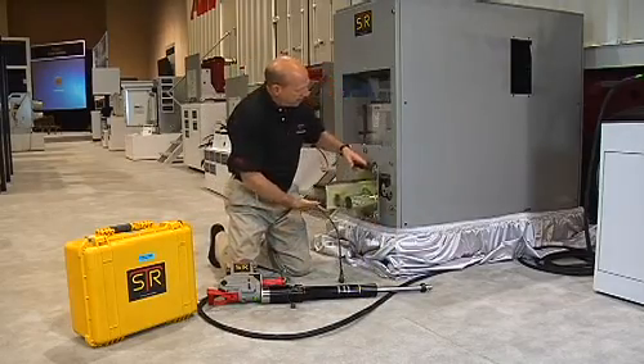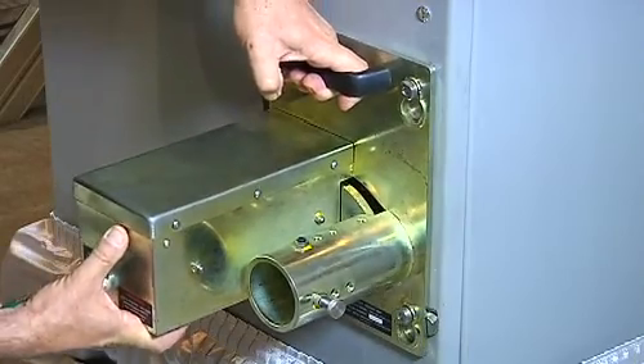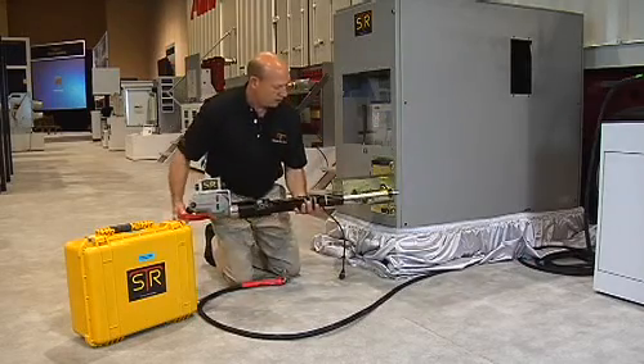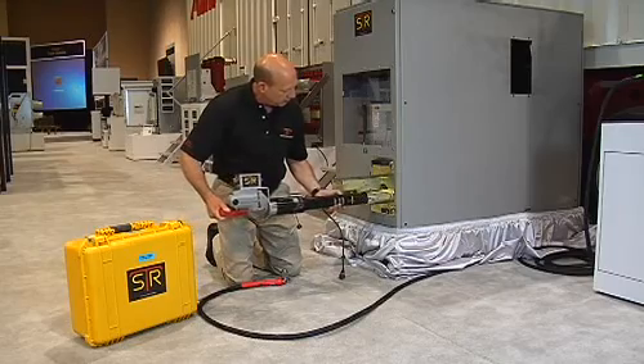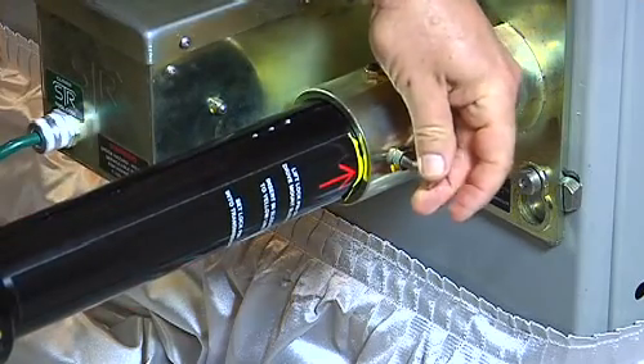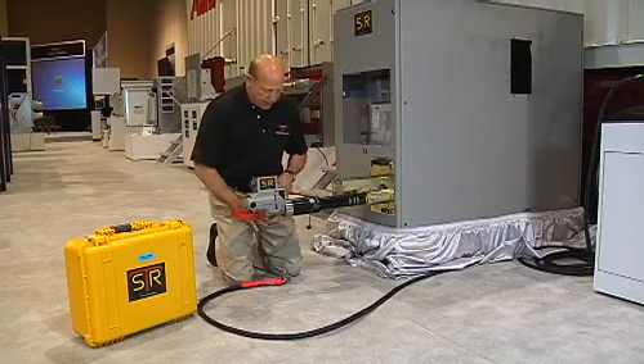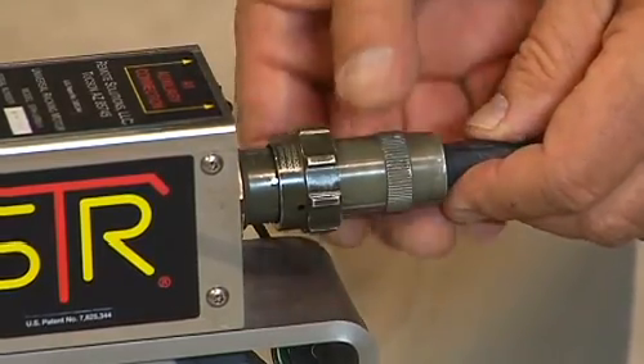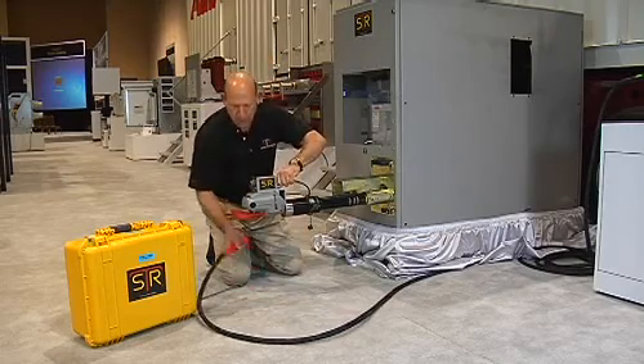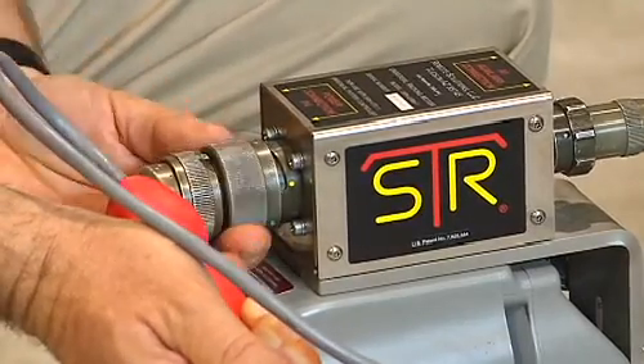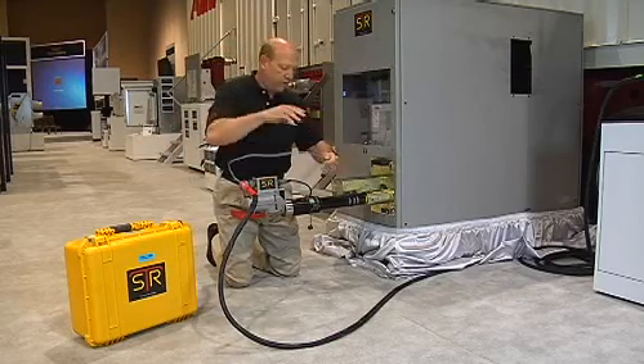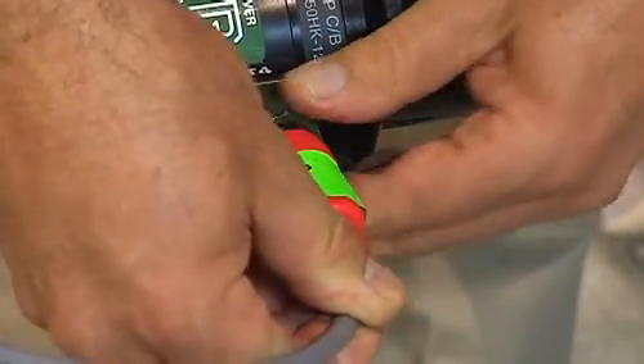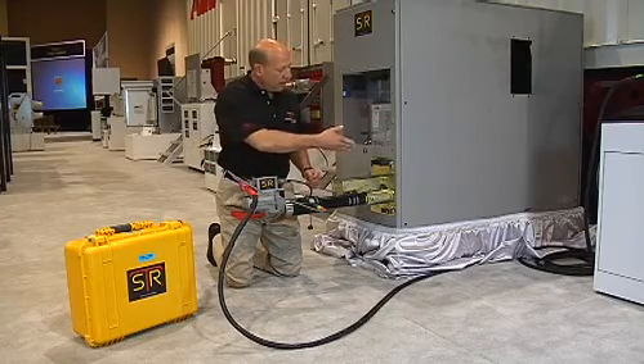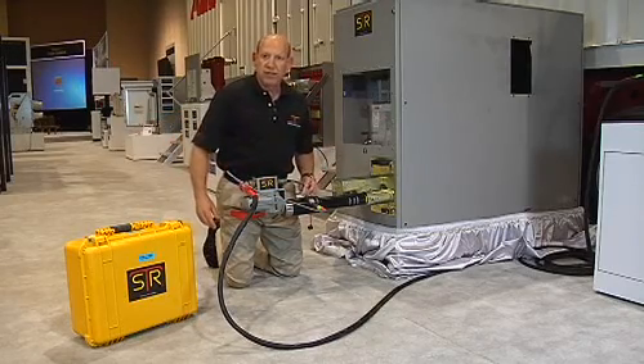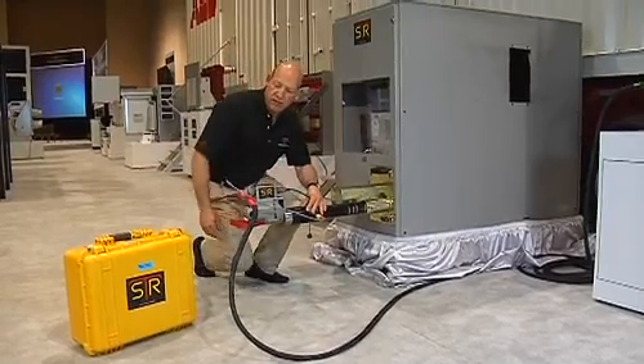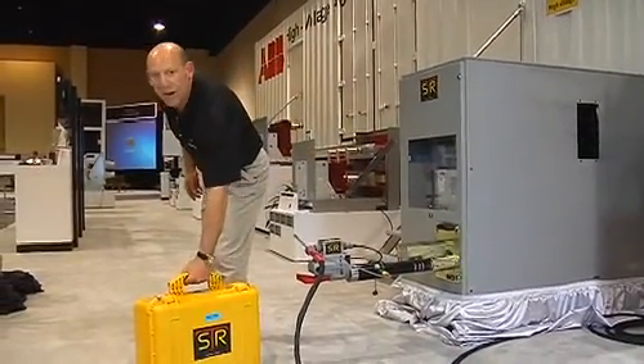Take the transmission drive bracket assembly, mount it on the door. Install the drive transmission and motor assembly into the drive bracket, locking it in place, making the drive bracket power connection, the motor power connection, and the transmission data connection. At that point, we will extend our power comm cable out to a safe distance, taking out all the slack, take our system controller, and make our connections, prepare for racking.